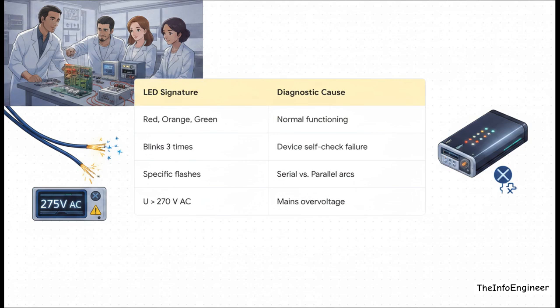But what makes these devices truly pro-grade are the built-in diagnostics. It's a massive time saver for engineers in the field. Just by reading the specific LED flash sequences on the device after a trip, you can decode exactly what went wrong. The device actually tells you if it tripped because of a serial arc from a damaged wire, a parallel arc between line and neutral, or even if the mains overvoltage spiked past a dangerous 270 volts AC. It totally eliminates the guesswork from your troubleshooting.